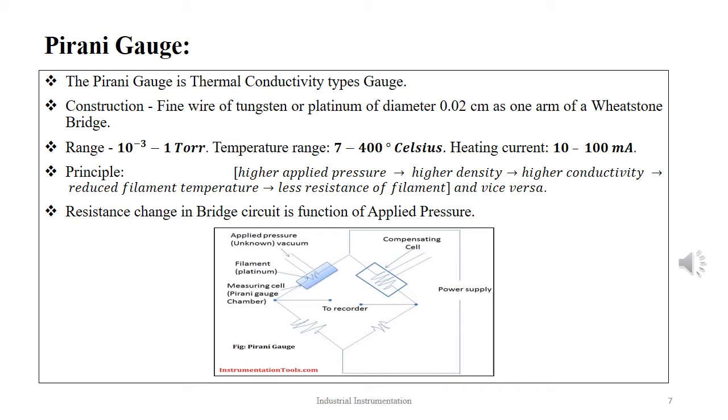The principle of operation is given as higher applied pressure leads to higher density, leads to higher conductivity, thus reducing the filament temperature, thus reducing the filament resistance, and vice versa for low pressure.